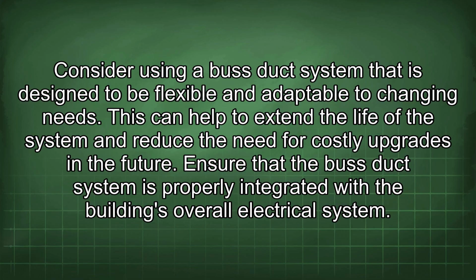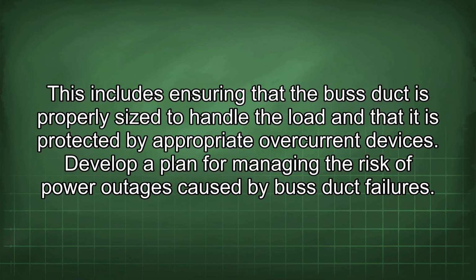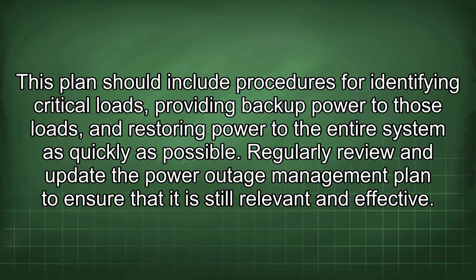Ensure that the bus duct system is properly integrated with the building's overall electrical system. This includes ensuring that the bus duct is properly sized to handle the load and that it is protected by appropriate overcurrent devices. Develop a plan for managing the risk of power outages caused by bus duct failures. This plan should include procedures for identifying critical loads, providing backup power to those loads, and restoring power to the entire system as quickly as possible. Regularly review and update the power outage management plan to ensure that it is still relevant and effective.